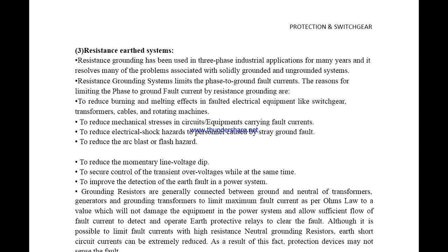Due to the resistors, the short circuit current may also get reduced. As a result, the protection devices may not sense the fault. This is a main disadvantage, because the short circuit current may flow through the resistance also. So in that case, the sensing of the fault may be missed.